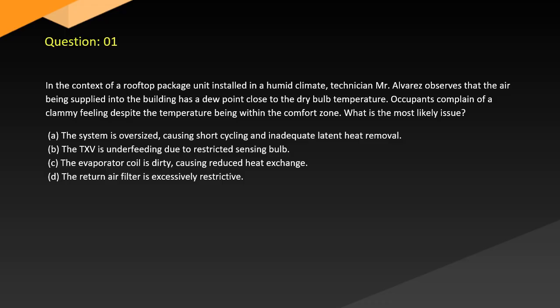Question 1. In the context of a rooftop package unit installed in a humid climate, technician Mr. Alvarez observes that the air being supplied into the building has a dew point close to the dry bulb temperature. Occupants complain of a clammy feeling despite the temperature being within the comfort zone. What is the most likely issue?